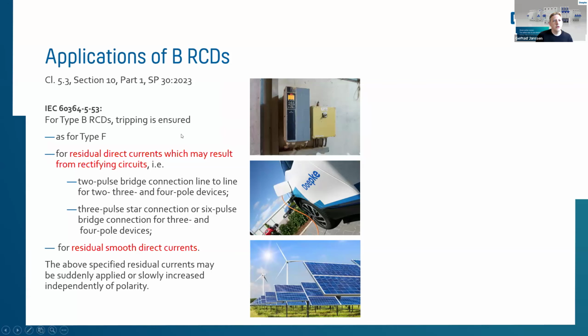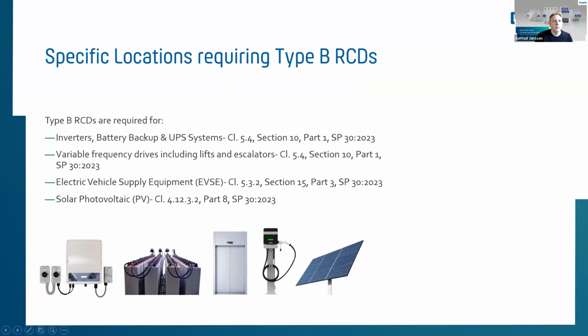Yeah, to explain a bit where the tripping is ensured: with the type B, it covers the A, AC and F types. Residual direct currents may result from rectifying circuits, also applications with 2-pulse bridge connections, line to line, for 2, 3 and 4-pole devices, and additionally the 3-pulse star connection or 6-pulse bridge connection. In all those applications, you are on the safe side with a type B RCCB. You see already on the right side some of the applications: solar photovoltaic or charging stations. Those are specific locations requiring type B RCCBs.